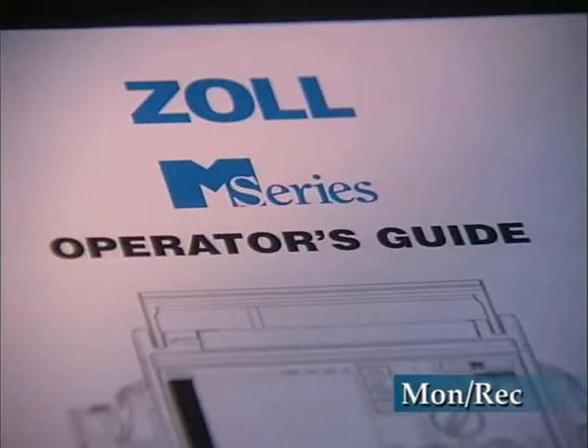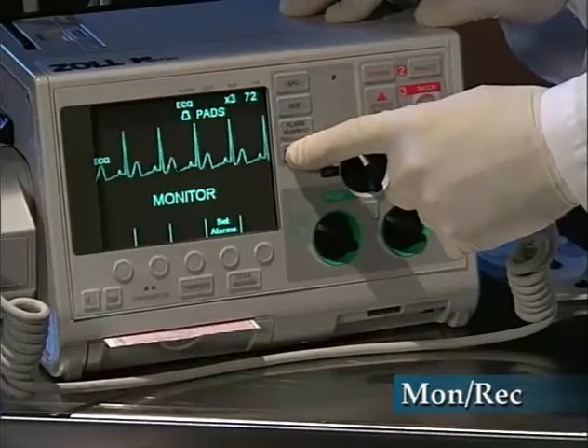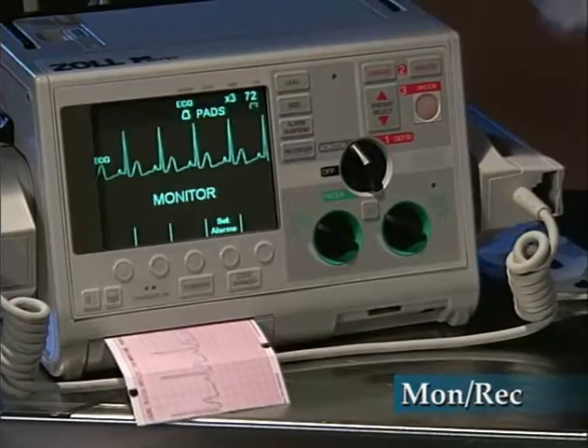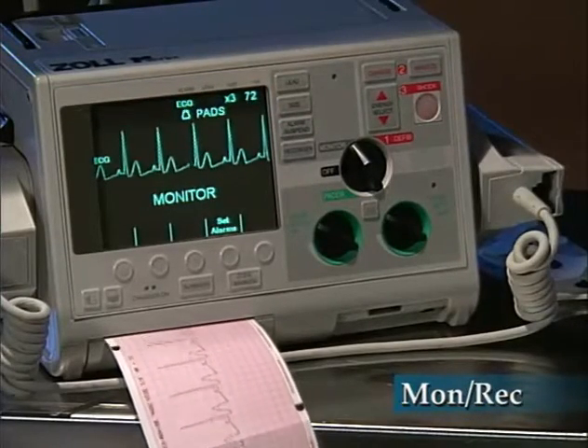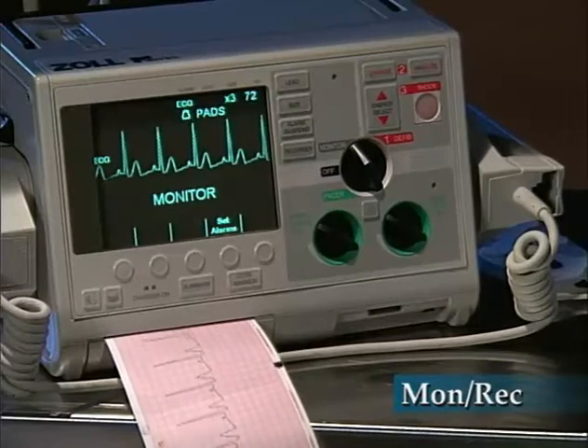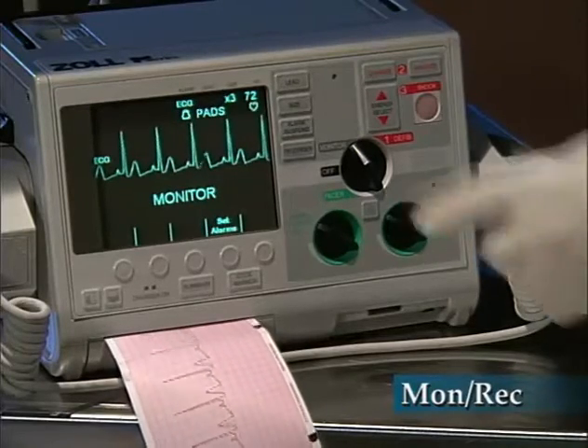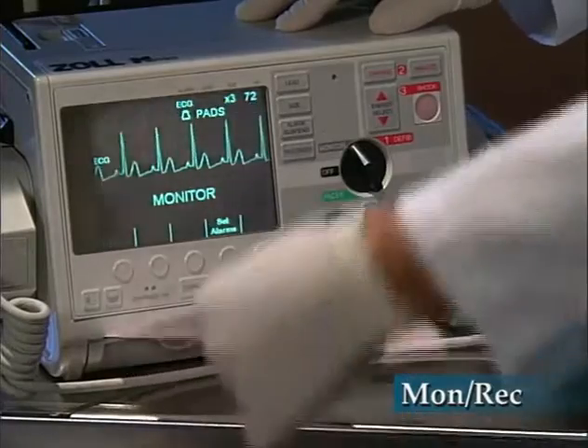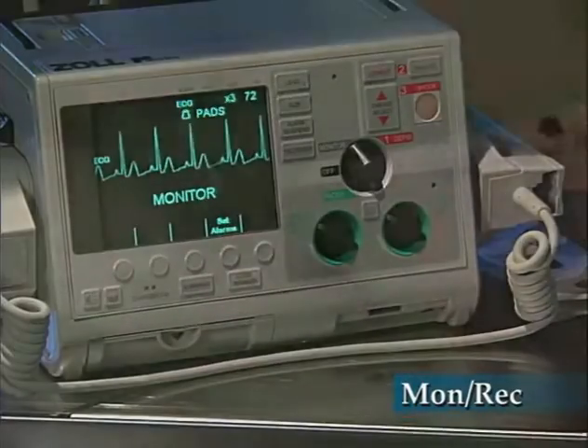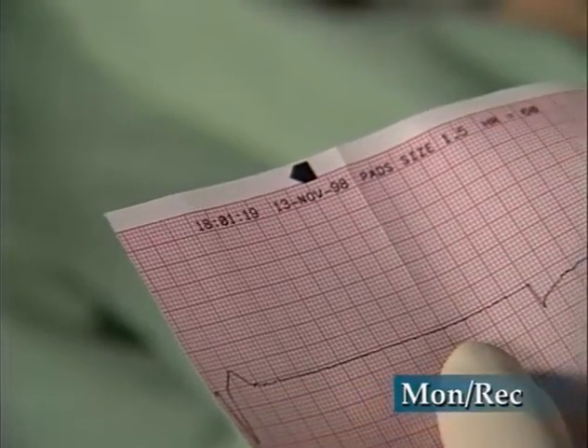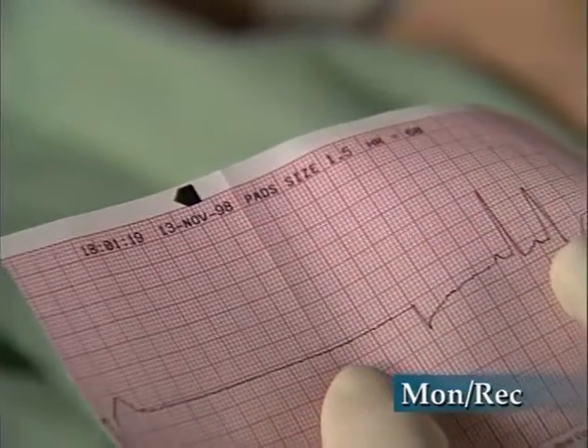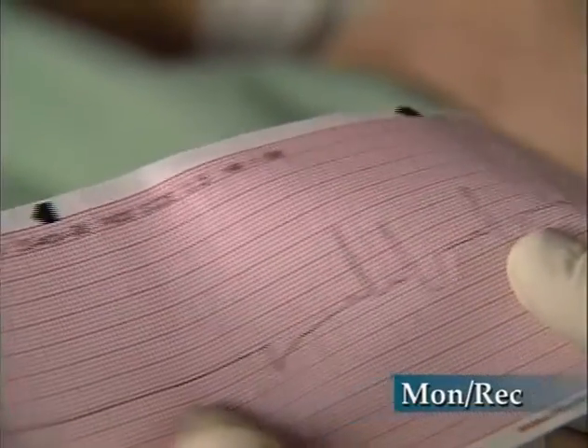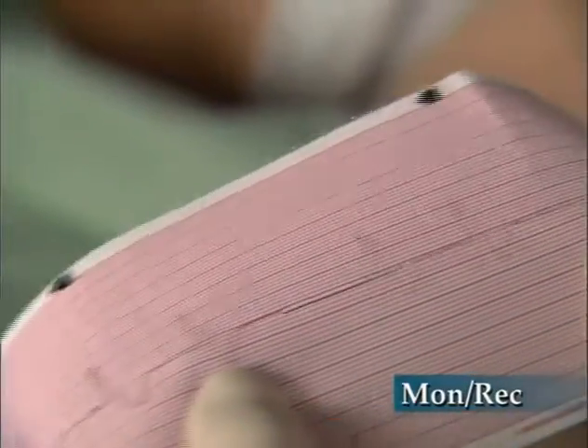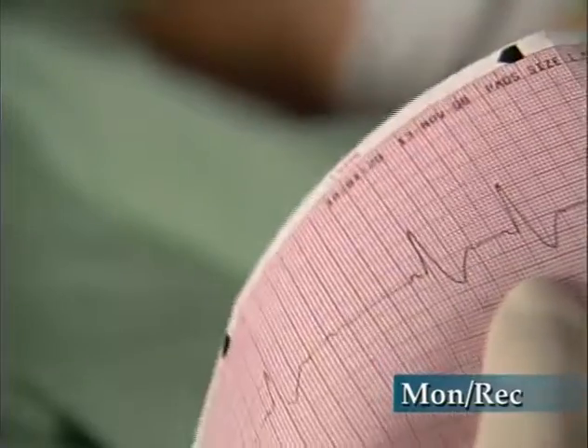Complete information on alarms is available in the operator's guide. The printer documents the ECG with a 6-second delay and can be programmed to automatically run when an alarm or a defibrillation event occurs. Press the recorder button to start and stop the printer. ECG time, date, lead, size, and heart rate, and any other monitored parameters are documented. If pacing, the output current will be printed, and delivered energy will be printed when the defibrillator is discharged.